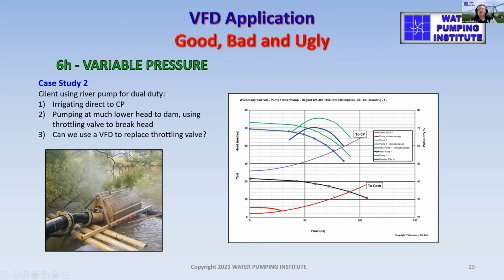If you put a throttling valve on there, you can still maintain around about 1,000 gallons a minute. But what happens if you were to put a VFD on there to achieve the same and save the energy wasted by the throttling valve? Well, if you applied a VFD to that curve, the end of the curve goes down in this direction, and there's the pump curve at the first opportunity that it contacts this system curve to the dam. At that point, we're only pumping 500 gallons a minute instead of 1,200 gallons a minute out here. So the farmer is not achieving the ends. He's not getting the pumped flow because of the effect of the VFD. It actually slows the output.